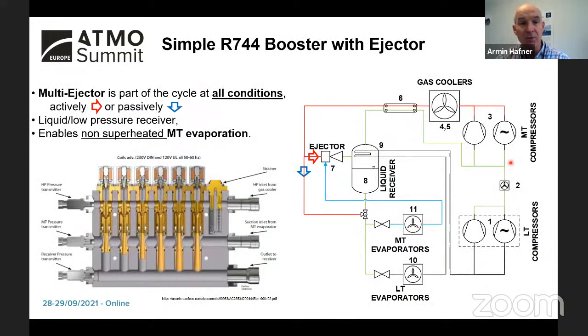When it comes to booster systems and ejectors, we have seen a lot of interesting innovations in the last year, and now it's going a little bit back to simpler systems to make this a global application. On the right-hand side, you see a simple booster system. It has an ejector there, but what we want to show is that it is possible to replace the high pressure control valve with the ejector, and then have an ejector system which can utilize this nice advantage of utilizing the expansion work all year. And in case of utilizing such a multi-ejector, it has so many functions inside, which I would like to show you, which enable this.